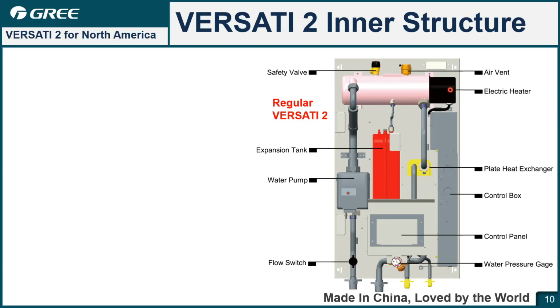In case of some situation, you need the e-heater to heat the water, increase the temperature. This one is the air vent for discharging the air inside. Here is a safety valve. If the pressure is too high, this valve will open to release the pressure. And this one is the expansion tank to balance the pressure and store the expansion water. This one is the water pump for circulating the water inside, and this is the flow switch to detect the water flow. So this one you can see in this slide is the regular VERSATI 2 for the European market.